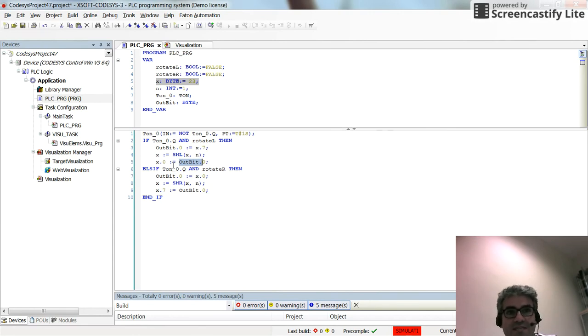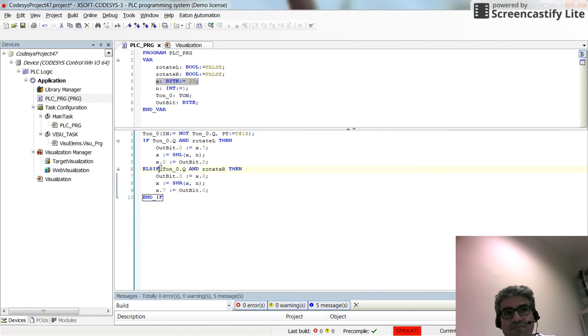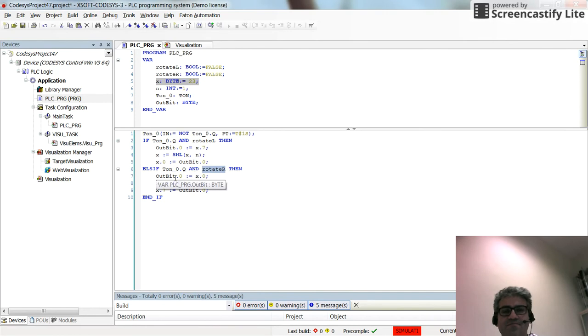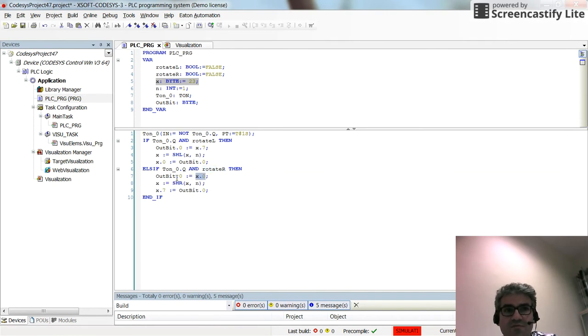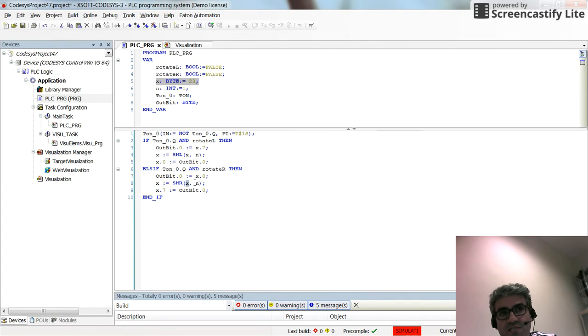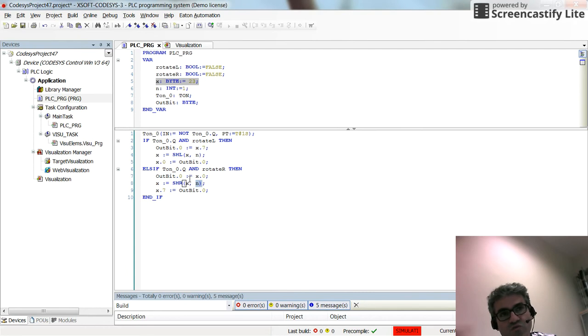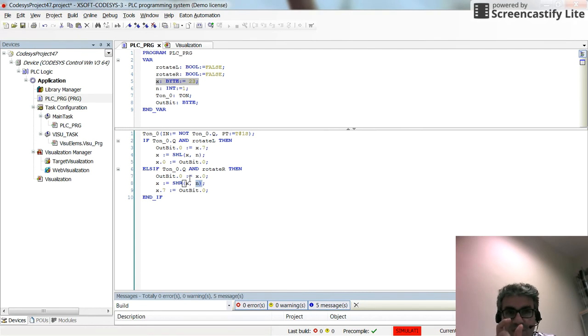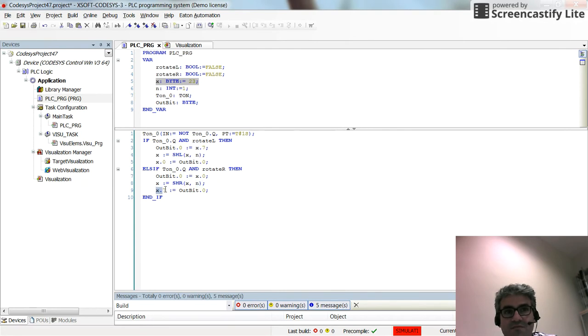On the other hand, if we have the timer done, if 1 second has passed and rotate R is true, then we will have the first bit of X, X.0, stored in OUTBIT.0. Then X will receive the SHR shift towards right of X and N. Again N is 1 and X will be shifted towards right side this time, with 1 bit to shift. The last bit of X will receive the value from OUTBIT.0, which is originally X.0.